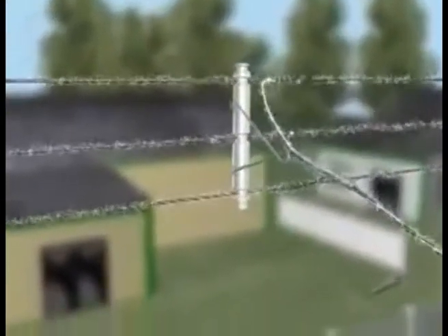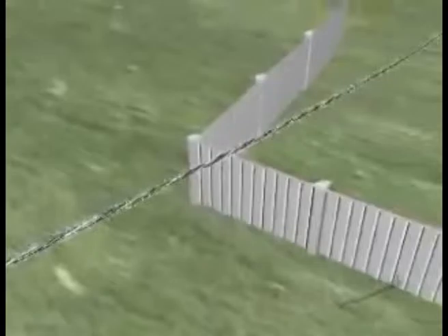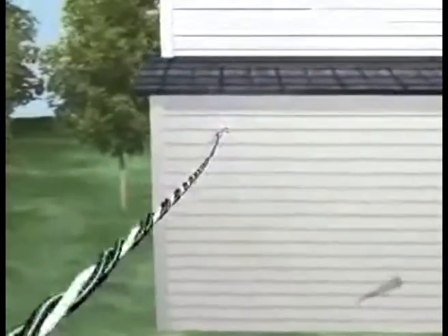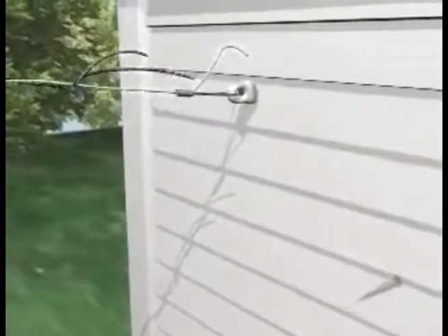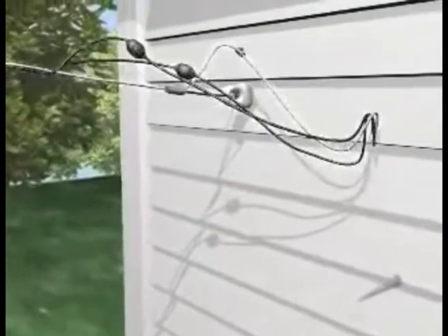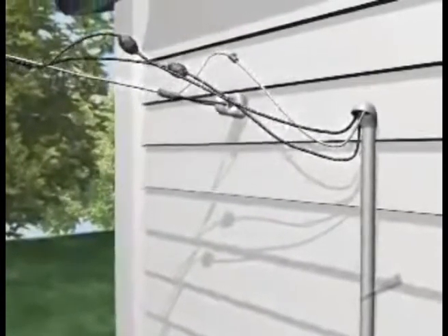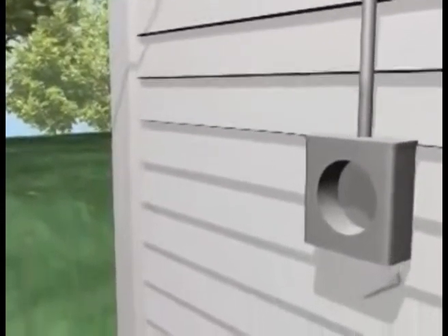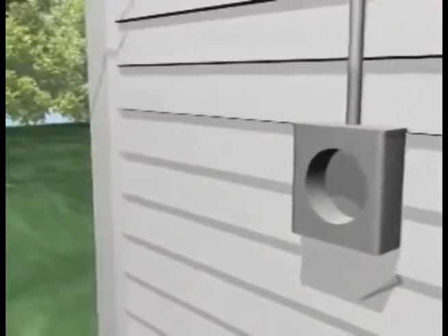The lines that connect directly to your house are called a service drop. An overhead service is generally a twisted set of 3 wires. Usually the service drop is connected to the home with a knob. The knob supports the weight of the wires, and the electrical connection is made at the weatherhead. The weatherhead is designed to prevent rain from getting down into the wires, leading to the meter base.